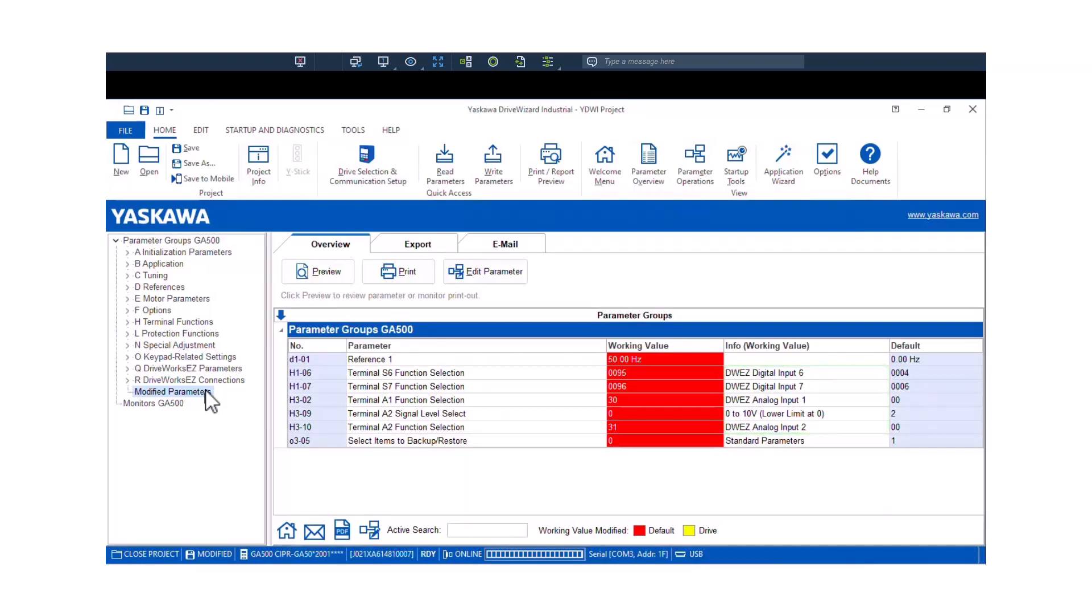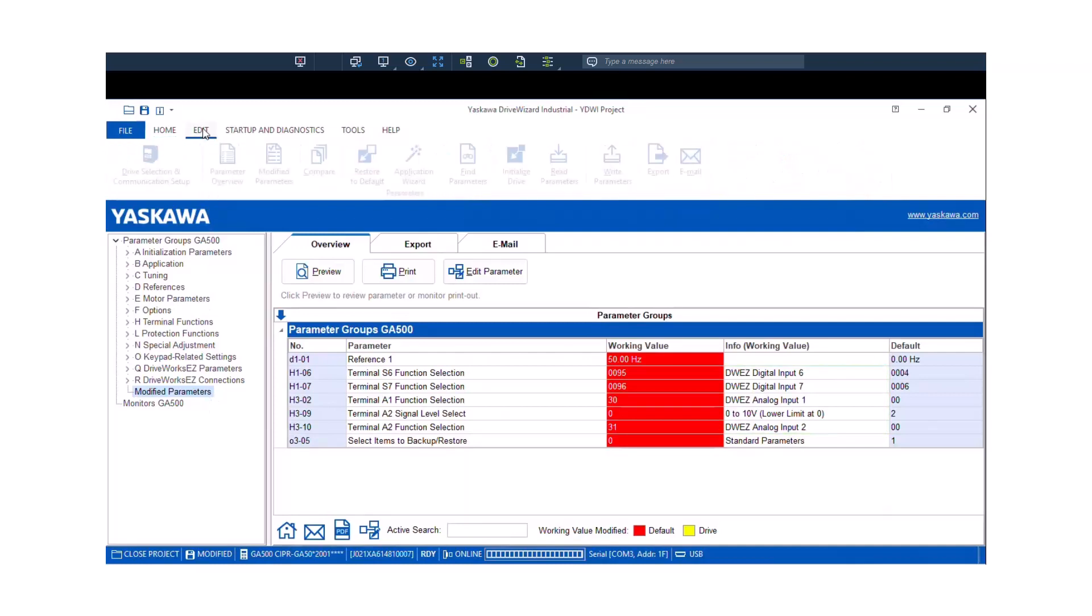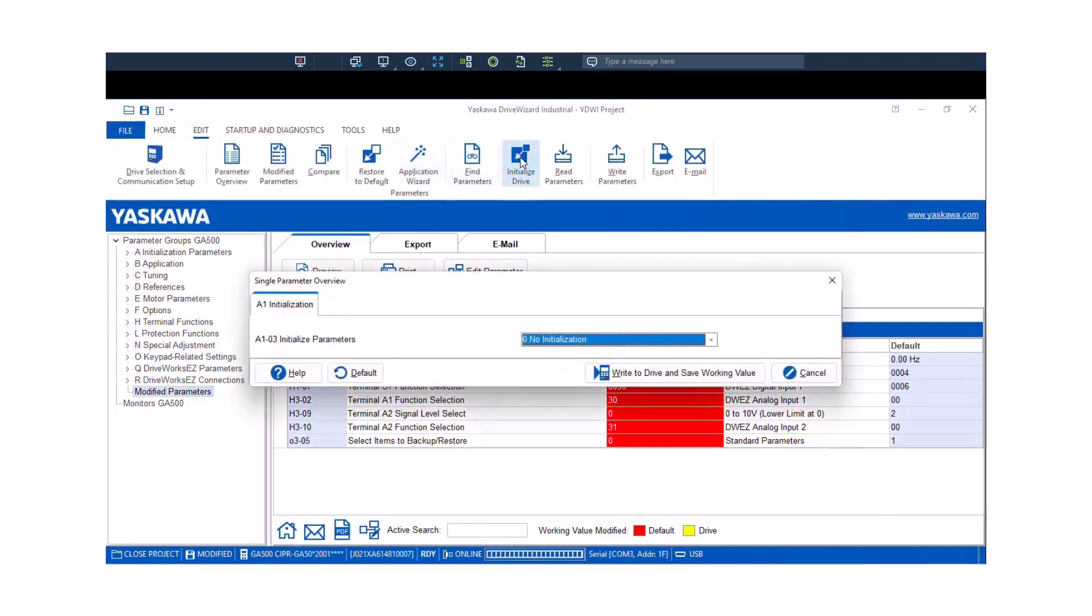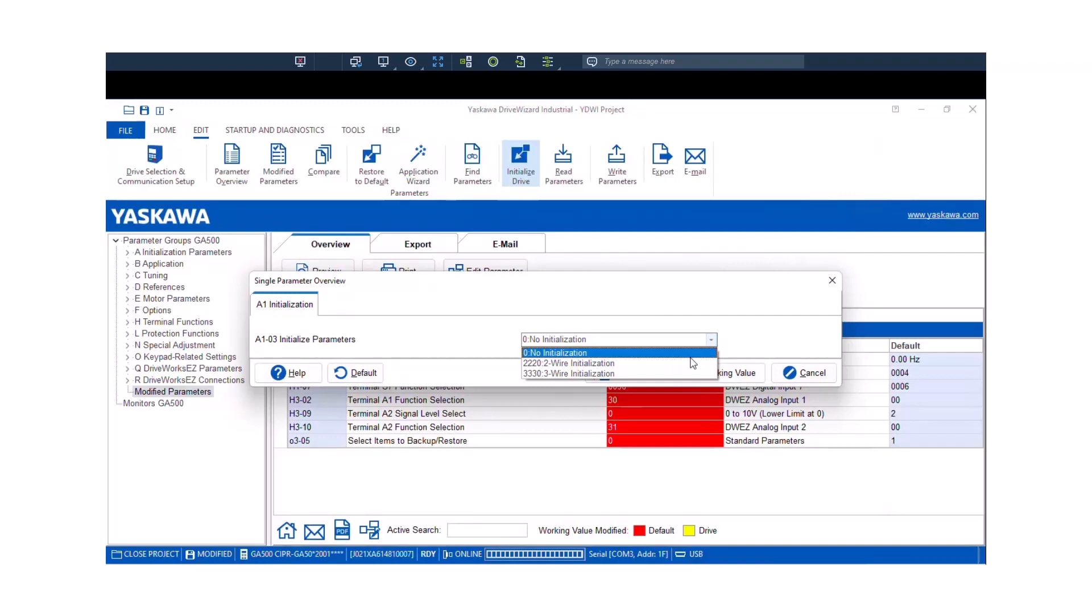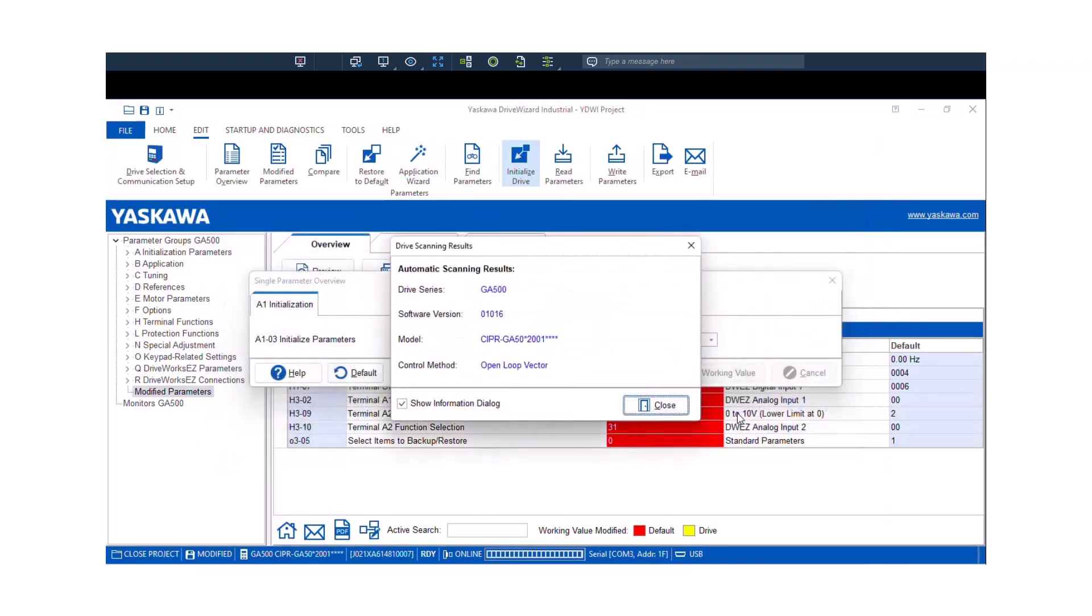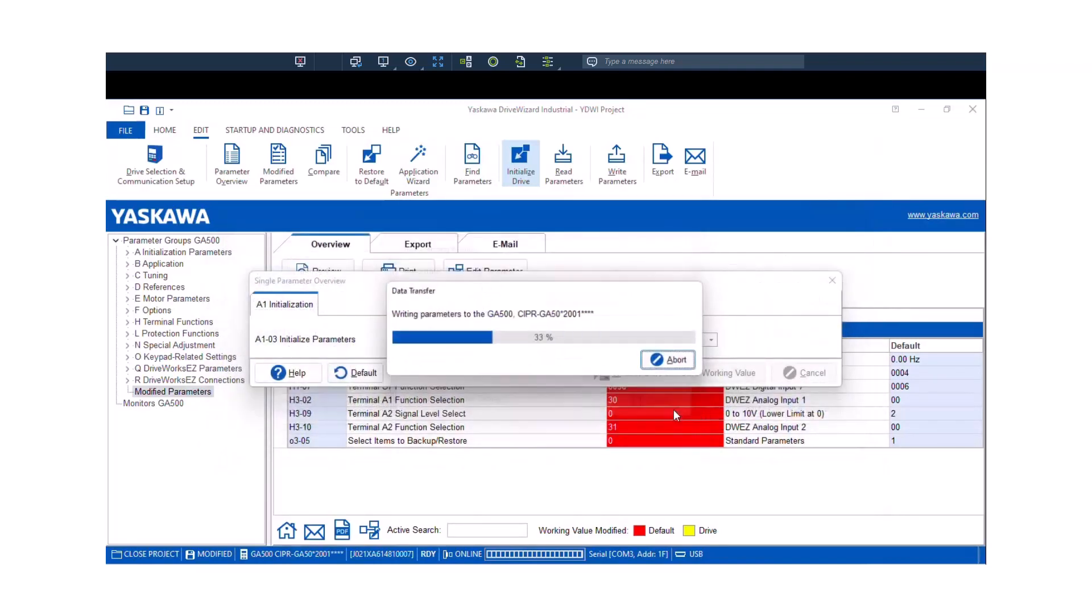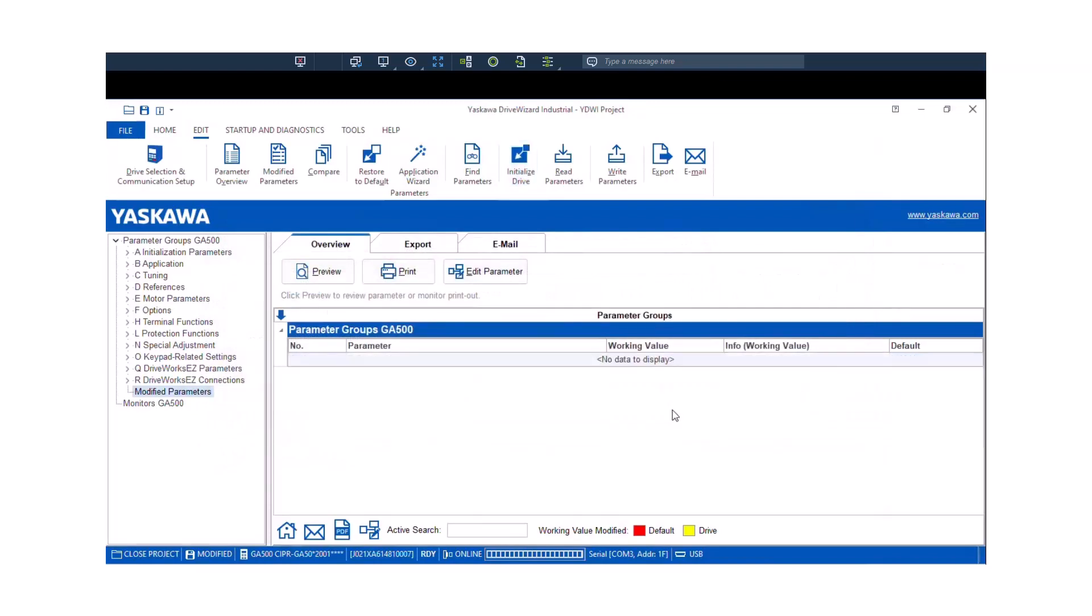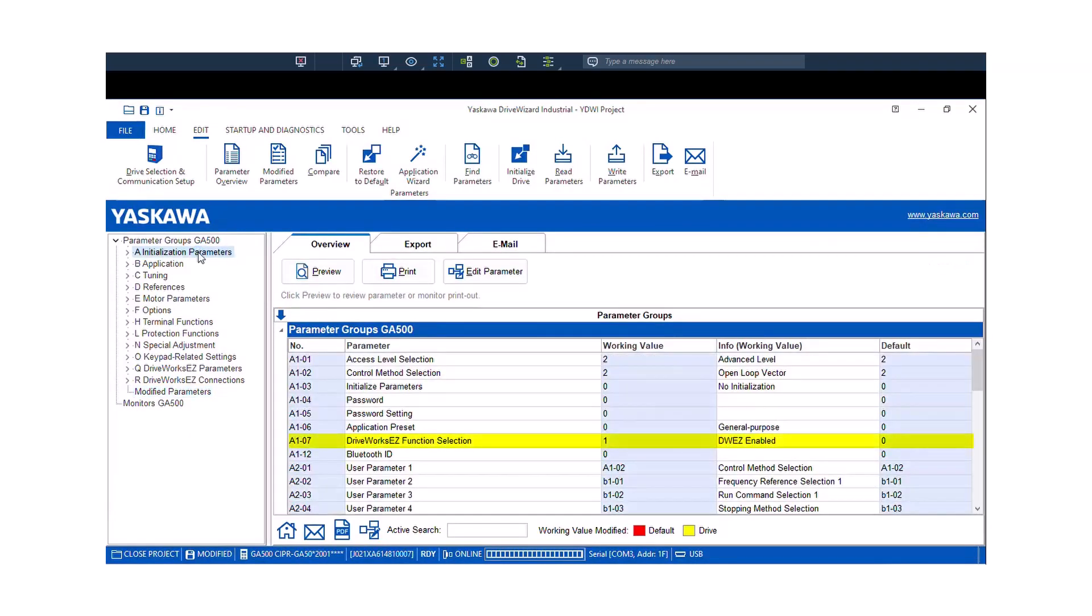So if we'd like to restore the drive back to default, what we can do is we can go up to the Edit tab and you can initialize the drive by clicking the Initialize Drive icon. A 2220 or a two-wire initialization is a standard factory default, so I'm going to click that and set. There's a handful of parameters that do not get reset to factory default upon an initialization, and A107 is one of them, and that's actually a good thing.